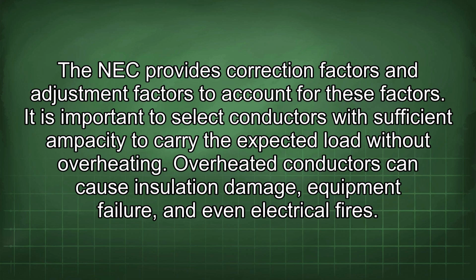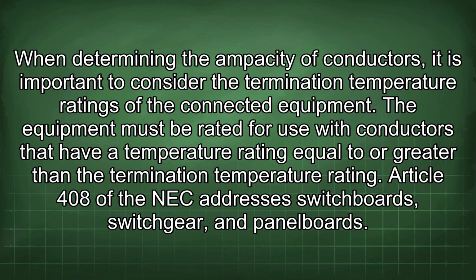It is important to select conductors with sufficient ampacity to carry the expected load without overheating. Overheated conductors can cause insulation damage, equipment failure, and even electrical fires. When determining the ampacity of conductors, it is important to consider the termination temperature ratings of the connected equipment. The equipment must be rated for use with conductors that have a temperature rating equal to or greater than the termination temperature rating. Article 408 of the NEC addresses switchboards, switchgear, and panel boards.